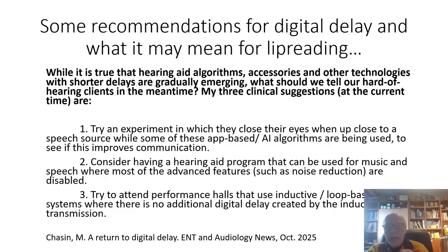Also, consider having a hearing aid program that can be used for music and speech, where most of the advanced features, such as noise reduction, are disabled. So even though the hearing aid nominally has a digital delay of 5 or 3 or 1 or even less than 1 milliseconds, that won't be the case when some of the more advanced noise reduction techniques are involved.